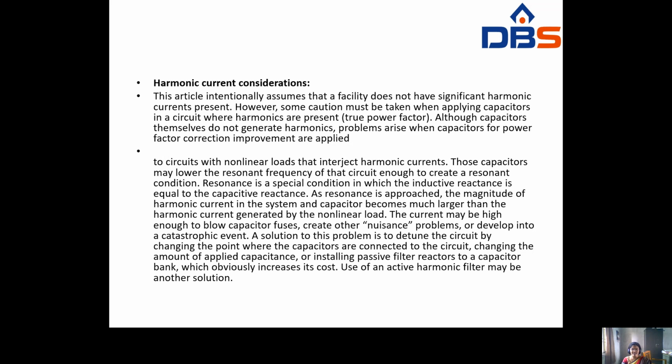Another way is installing passive filter reactors to a capacitor bank, which obviously increases its cost. Use of an active harmonic filter may be another solution.